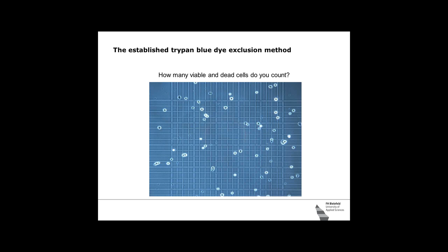So counting cells and the errors that occur are not human errors alone, like preparing the Neubauer chamber and having a particle of dust of 10 microns between the slide and the chamber. That would result in the worst case in 10% deviation of the cell count. But it's not that alone. It's simply that every user has a certain bias of how to count viable cells and how to define dead cells. And that's basically why we feel and we see deviations between different operators if cells are being counted.